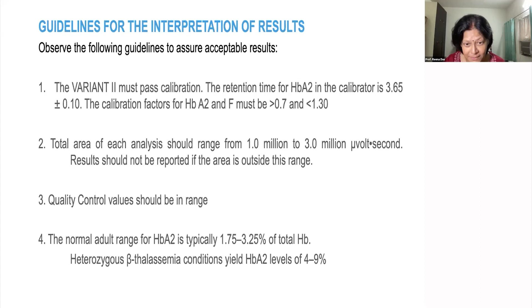And the calibration, the RT is called the retention time. The retention time is 3.65 plus minus 0.1 minutes. So if you look at the retention time of hemoglobin A2 here, you can see it is 3.66. The other important thing to remember is that the reading actually starts from 1 minute onwards.